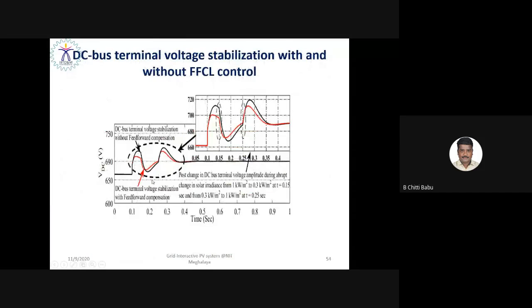And this is the DC link voltage stabilization with the previous controller that was proposed in the literature. You can see the peak overshoot as well as the steady state response. But with the help of the feed forward control loop, you see the DC bus voltage stabilization can happen with reduced peak overshoot as well as reduced steady state error. So that is the contribution that has been published in IEEE Transactions on Industry Applications.